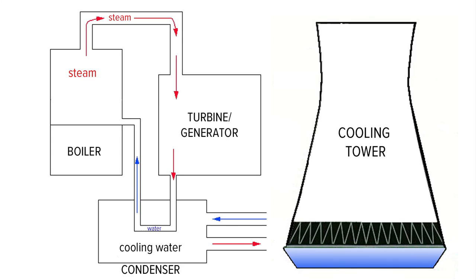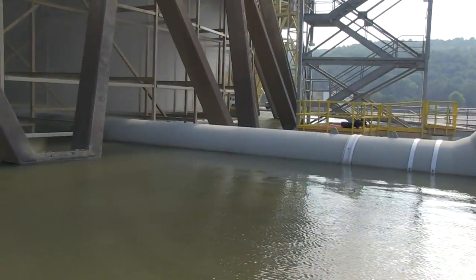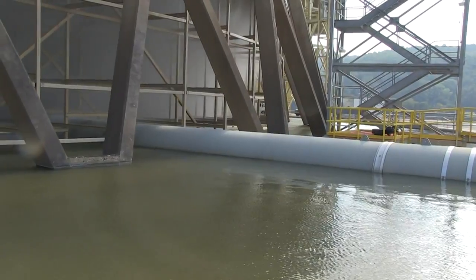steam. The warmed condenser water is pumped out to the cooling tower, where it cascades down over fill material that breaks the water into fine droplets. Air rushing through the base of the cooling tower naturally cools the droplets, which then collect in the base to be pumped back to the condenser.